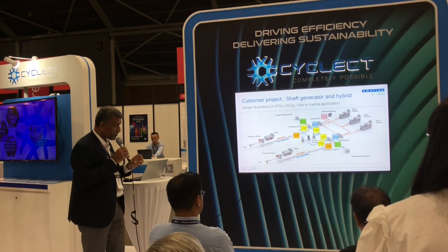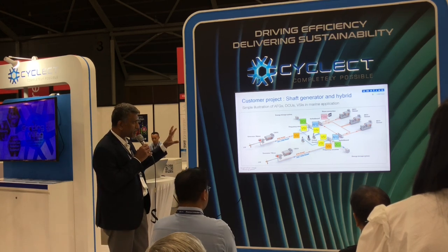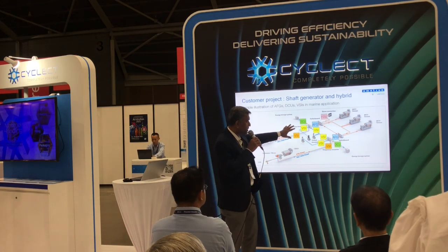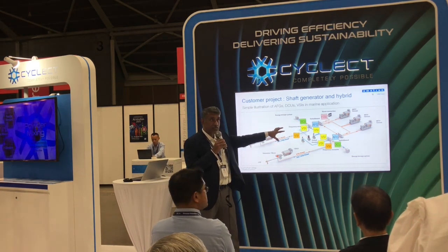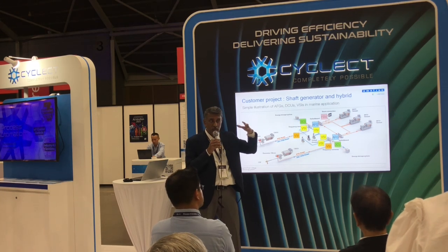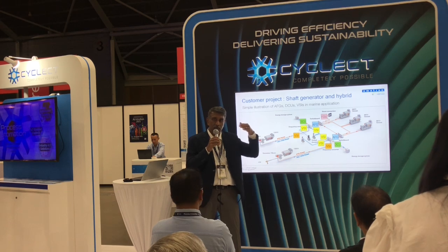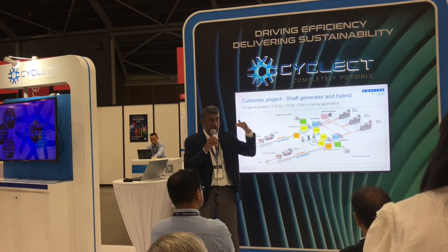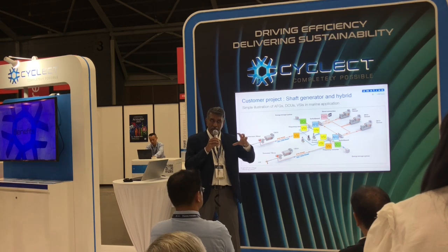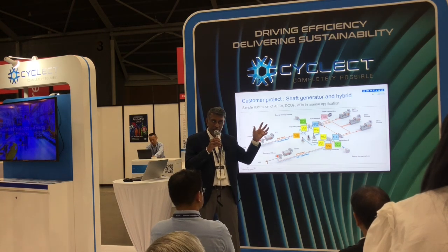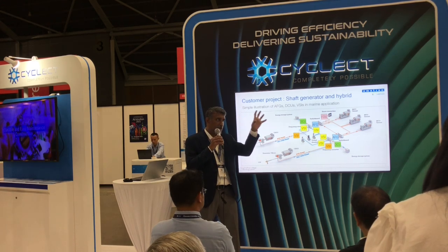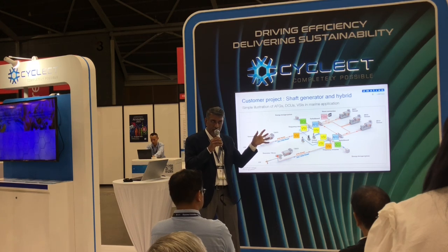I've shown you an example of what happens in a marine system where you have everything. You have the VSI, you have the DCU, you have the AFG, but you can have similar systems even in a process plant, for example. If you have a system where you cannot afford to have your plant stop for any purpose and you're worried that the grid can fail, you can have a battery backup with a DCU and an AFG so that in case of a power supply dip, the battery takes over, creates a grid, and your process plant can run. Okay?